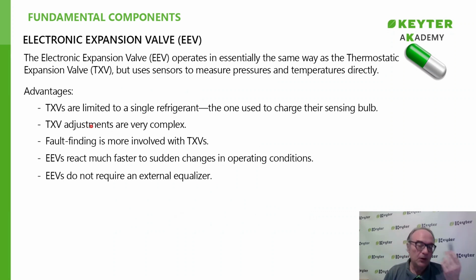Thermostatic settings are considerably more complex. Their fault analysis is also more intricate, and electronic expansion valves have a significantly faster measuring capability. If you remember, the thermostatic expansion valve had a bulb pressure that depended on the temperature of the bulb at the evaporator discharge, so that way of heating that gas and transmitting the pressure is slow. In addition to having a pressure transducer for instant data transmission, the electronic expansion valve does not need the balancer that was previously used to compensate and verify the accurate measurement of the bulb during strong pressure drops in the evaporator coil. This simplifies the system and improves efficiency by eliminating an additional component.